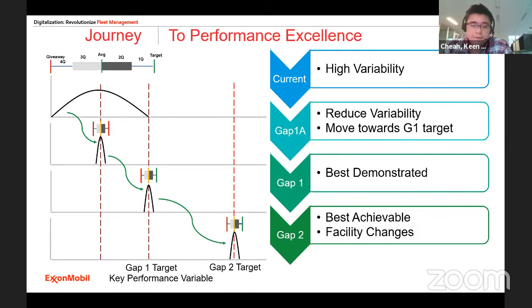The first step in the process is always to minimize variation. This is done by pushing the parameter closer to our constraint, and this optimization method pushes the plant towards operational excellence. This economic penalty in our GEMS, or global energy management system, is defined as gap 1A, where the lowest variance is considered the optimum, and what we want is to be operating at that optimum point.